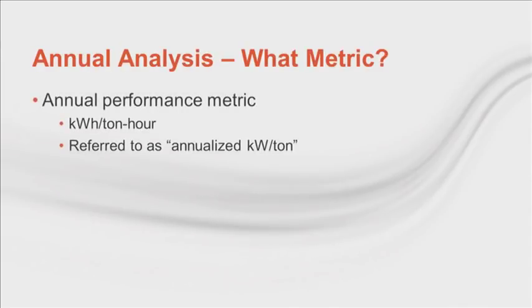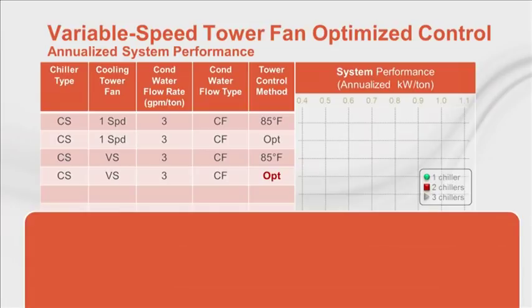To help us decide which design and control strategy to use, we'll calculate the annual energy efficiency for the system in terms of kilowatt hours per ton hours. By canceling the hours, we simplify the term to annualized kW per ton for the entire chilled water system. The base case is a constant speed chiller, single speed tower fan, condenser water design flow rate of 3 GPM per ton, a constant speed condenser water pump per chiller, and a tower controlled to maintain 85 degrees. We analyzed performance with 1, 2, or 3 chillers. The annualized kW per ton was drastically reduced with more chillers, but the difference from 1 to 2 was significantly greater than from 2 to 3.